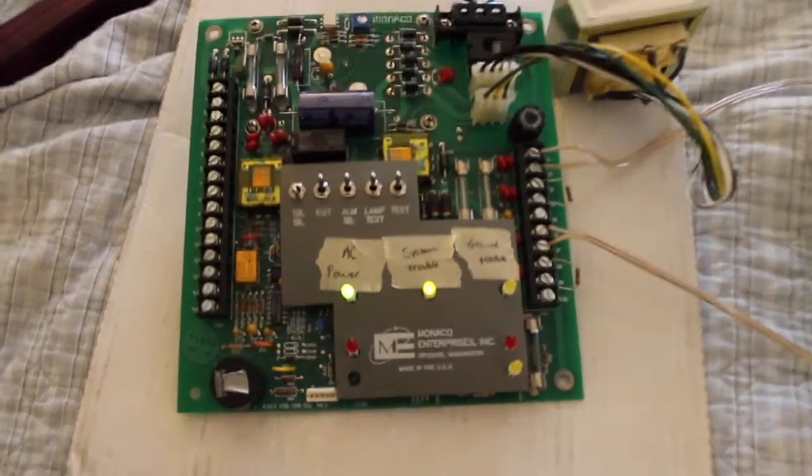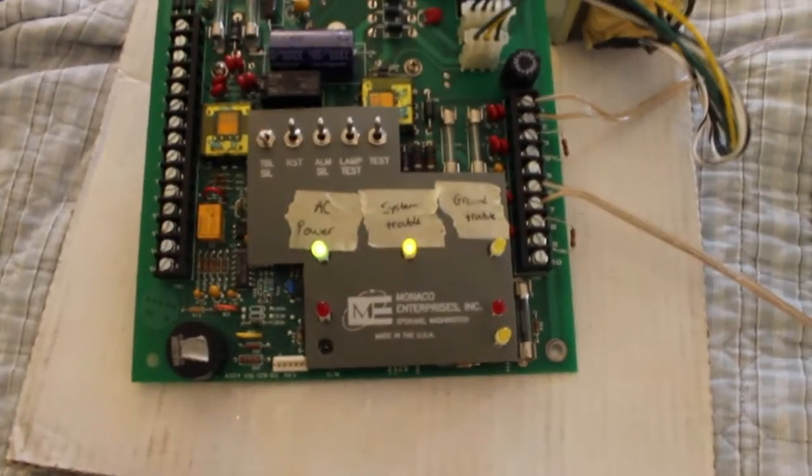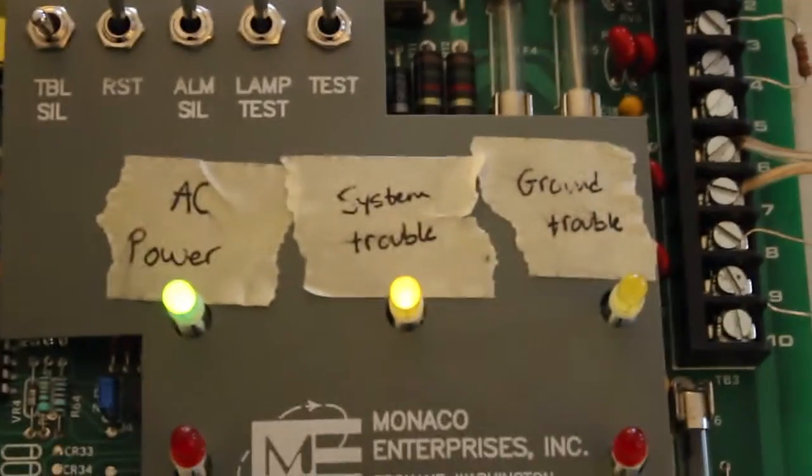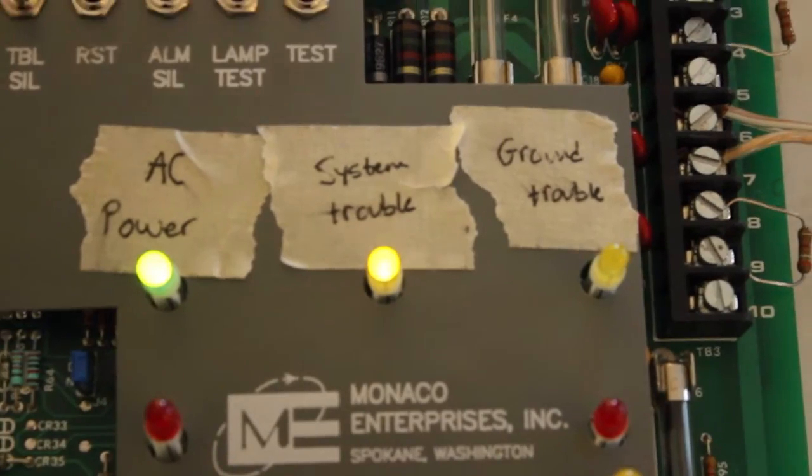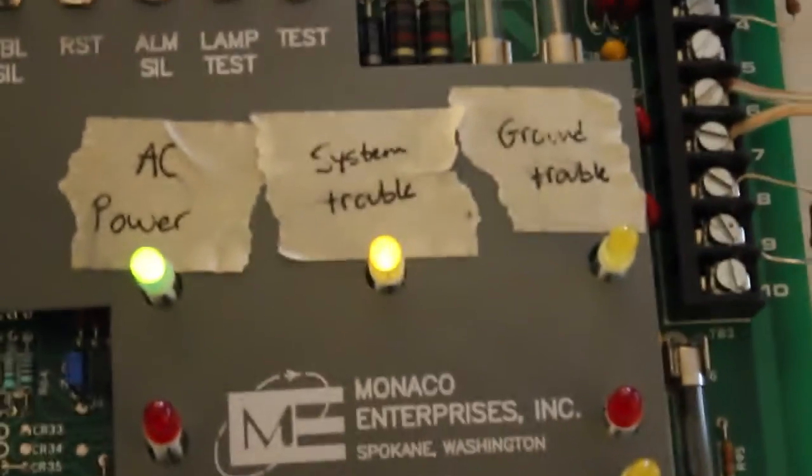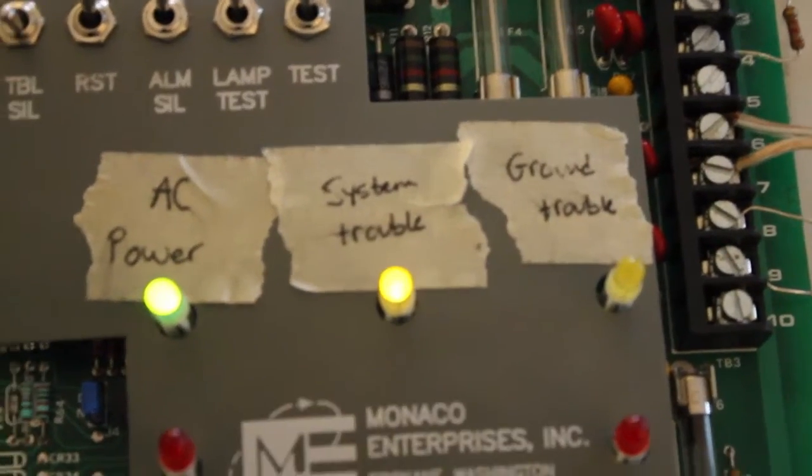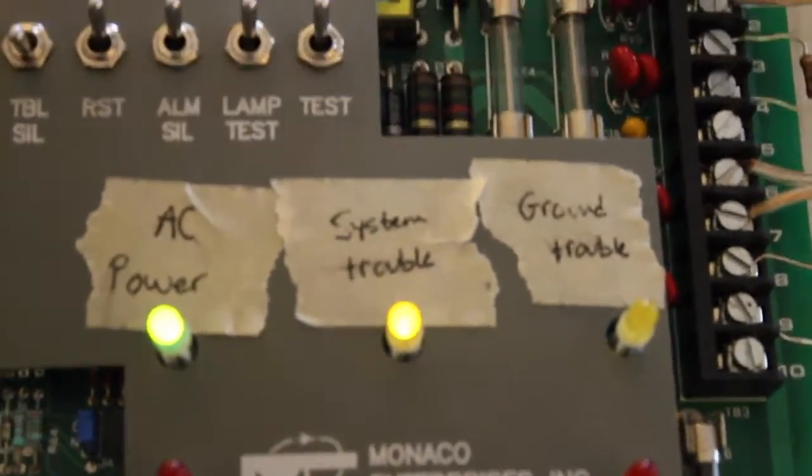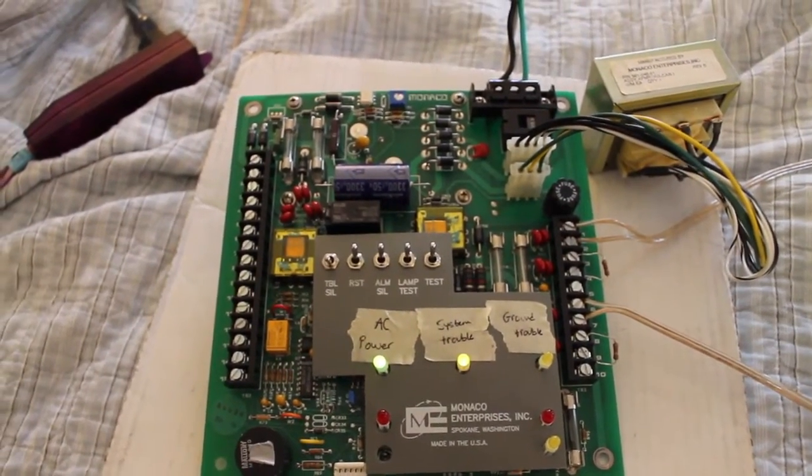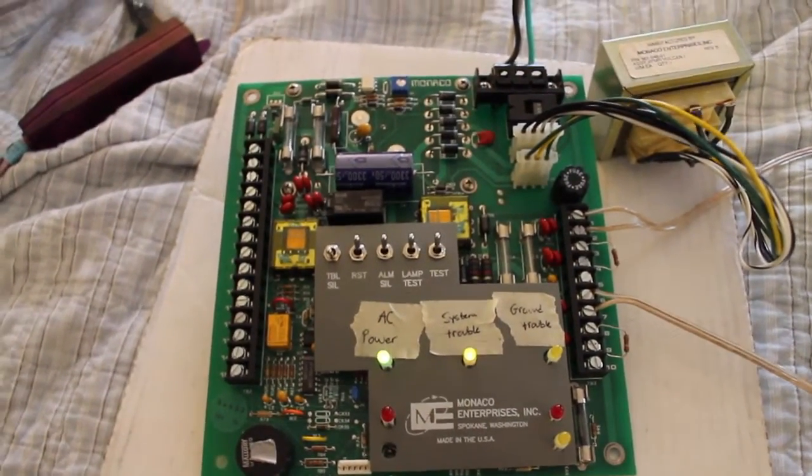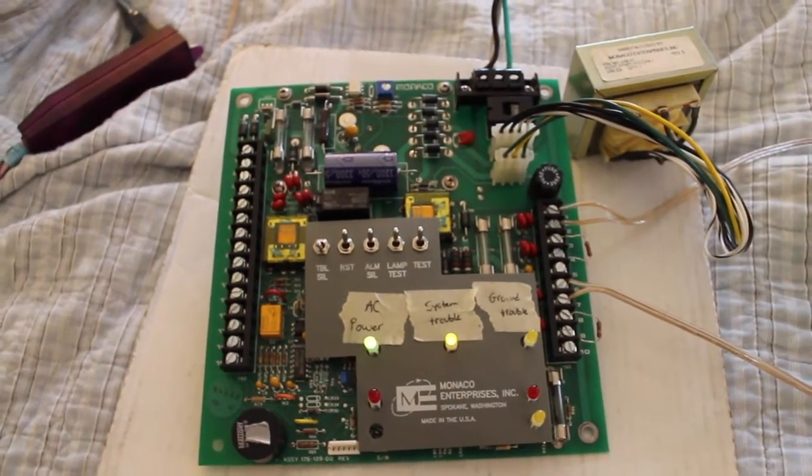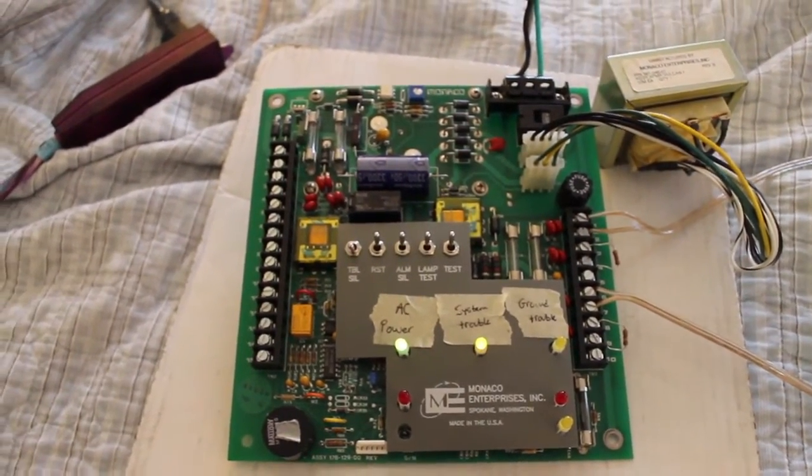So, you may notice I still have a system trouble. This system trouble light right here kind of indicates if there's a battery trouble or if there's a NAC trouble. It's all rolled into one light. So, the system trouble here is the fact I don't have any batteries. This is really just a temporary setup, so that hasn't been too big of a priority for me. Let's not dwell on that and move on with the test.